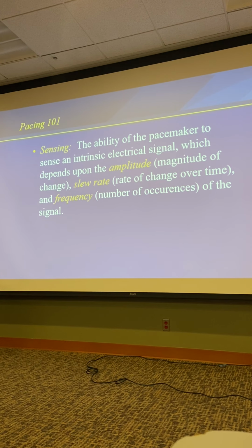Sensing is the ability of the pacemaker to actually see the signal, and it doesn't just look for the size of the signal. It looks for amplitude, slew rate, and frequency. Amplitude is how big the electrical signal is. Slew rate is how rapidly it's changing. So if a signal gets above the energy or the voltage necessary to be detected, but it's rising very slowly, the pacemaker knows the difference between that and something that rises very quickly, which is most likely an electrical signal from the conducting system of the heart. And the frequency, if the signal that it's seeing is occurring very, very rapidly or very, very slowly, it'll know not to treat it as electrical activity from the heart. So it uses all three of these criteria to try to decide if what it's seeing is a heartbeat or not.